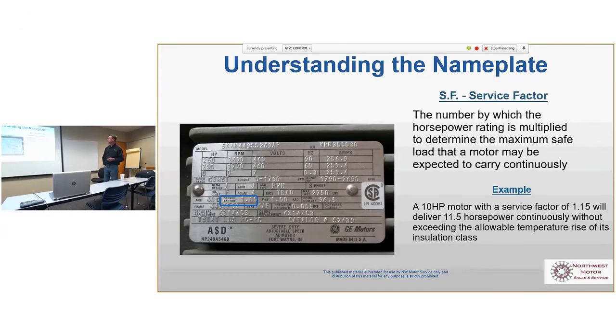Service factor: almost all motors are 1.15 service factor. All motors are 1.0 when operated on a drive. So if a motor has a 1.15 service factor, that means you can operate it at 115% of its rated nameplate ratings without causing harm to the motor. Now, that's the NEMA designation.